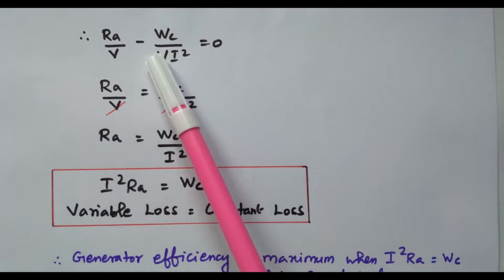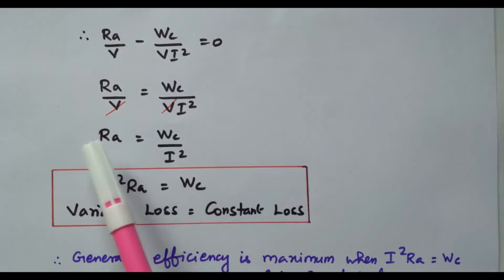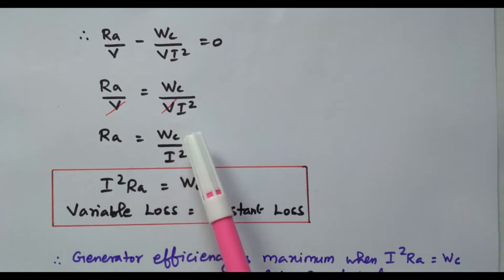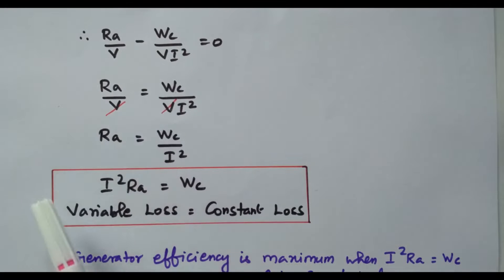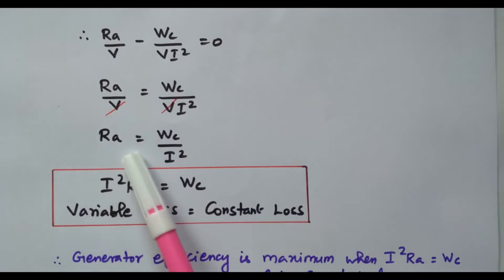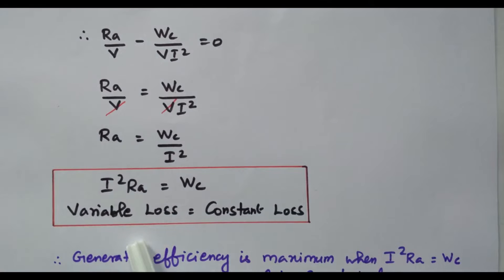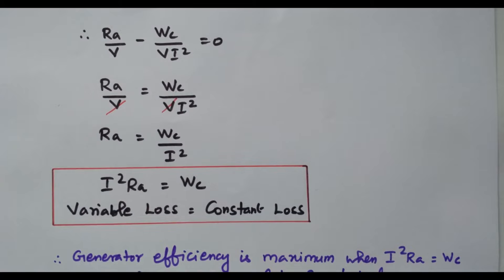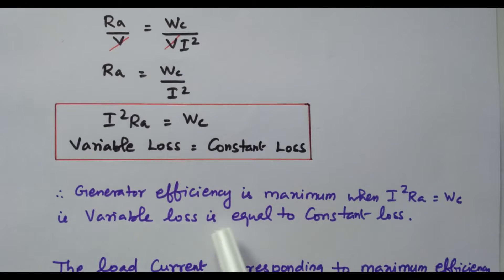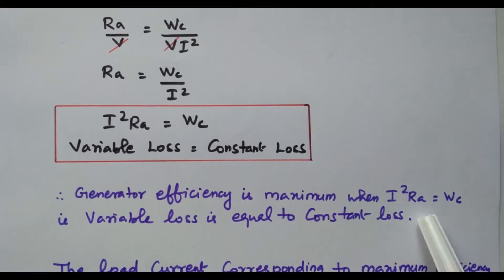Bringing the term to the right-hand side: RA/V = WC/(VI²). The V cancels on both sides, giving RA = WC/I². Rearranging: I²RA = WC. Here, I²RA is the variable loss and WC is the constant loss. So the condition for maximum efficiency is: variable loss equals constant loss. The generator efficiency is maximum when I²RA = WC.